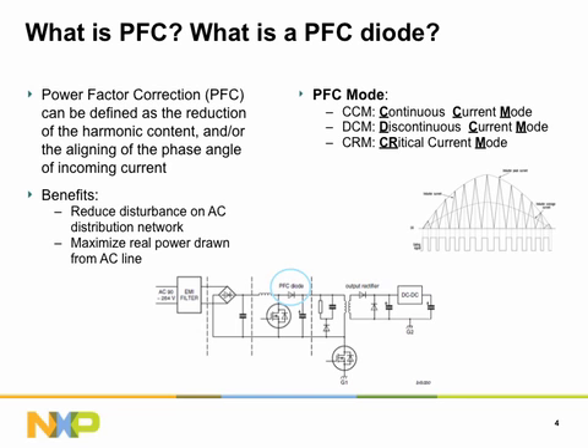Active PFC is related to reducing harmonic content and/or aligning the phase angle of incoming current. PFC is required to reduce disturbance on the AC distribution network and maximize the real power drawn by the power supply from the AC line.